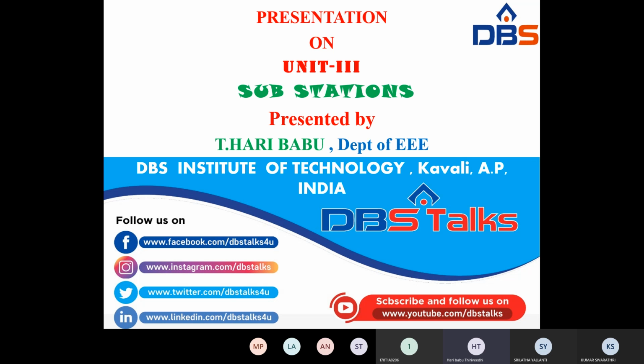Generally, the substation layout is nothing but a higher voltage being stepped down into lower voltages, and that lower voltage may be given to the consumer premises. Generally the incoming line of the substation is a 33 kV line, and that may be connected to the bus bar through the GO switch and lightning arrester. And from this bus bar, a number of feeders will be taken. So first feeder, second feeder.